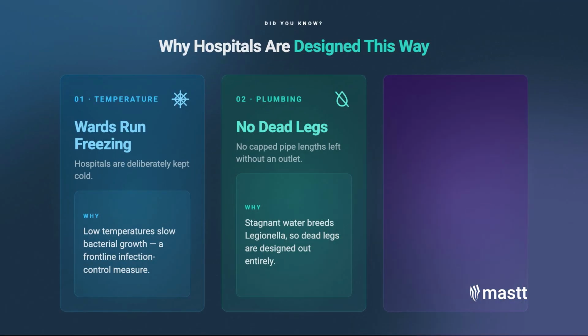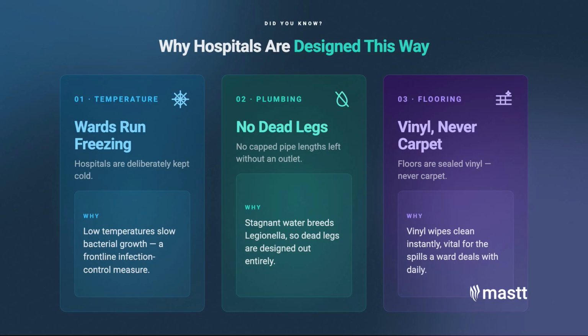But there are always issues we're picking up looking at ceiling space voids, like ductwork sitting too low, or dead legs in plumbing pipework, which bring risks. A dead leg is just a length of plumbing pipe which doesn't have an outlet at the end. In any normal project you'll have multiple dead legs, particularly in refurbishment projects where you cut off an outlet and just cap it and leave it. But in a hospital environment that creates a risk of Legionella, so you can't leave dead legs throughout a hospital build, you've got to bring it all the way back to completely remove those elements.